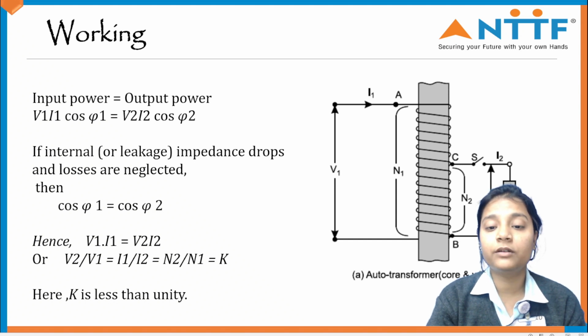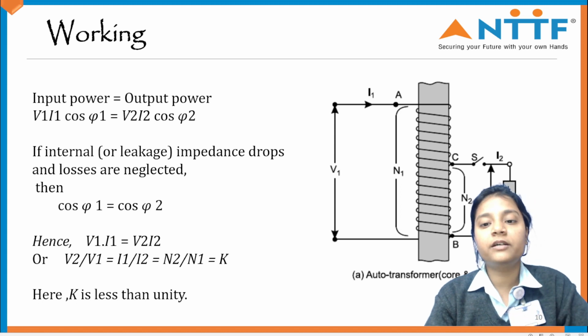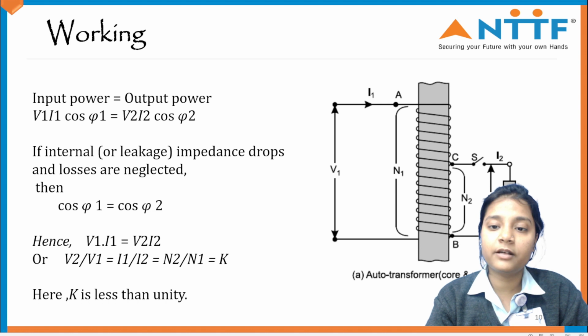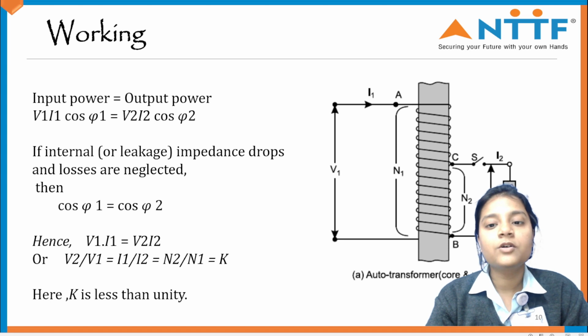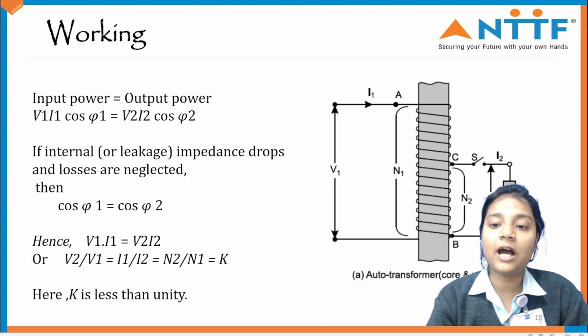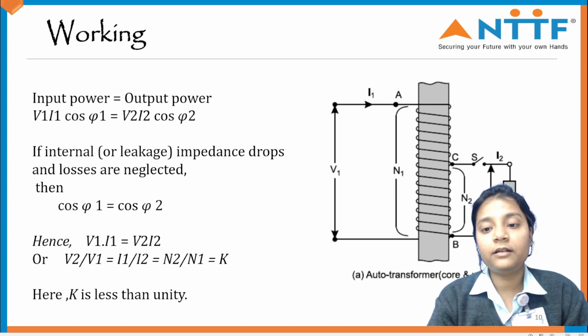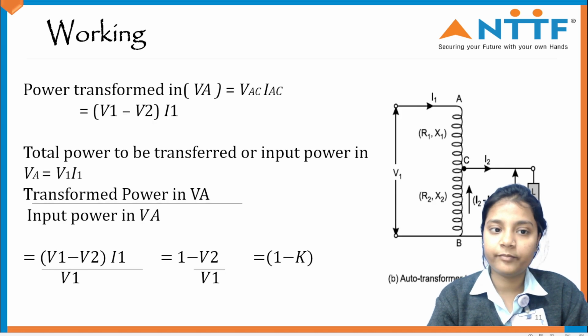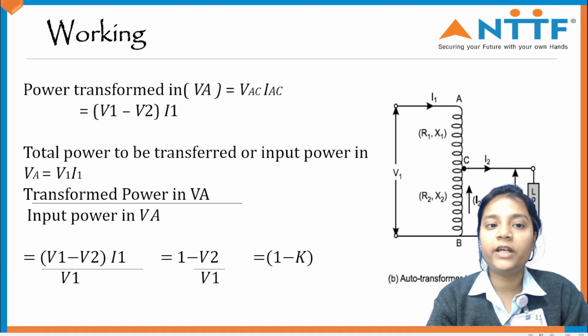The primary side is supplied with the AC supply of 230 volts. Generally we use 230 for a single phase transformer, and we also have a three phase transformer. Here I am talking about a single phase transformer. So we'll give a supply of 230 volts AC towards the primary side, and the secondary side has got tappings around the whole winding. The secondary side is not electrically isolated from the primary side, yet it is a magnetically coupled device. So the power transferred is always less than unity. So we can conclude that it cannot be used as a step-up transformer in that scenario.